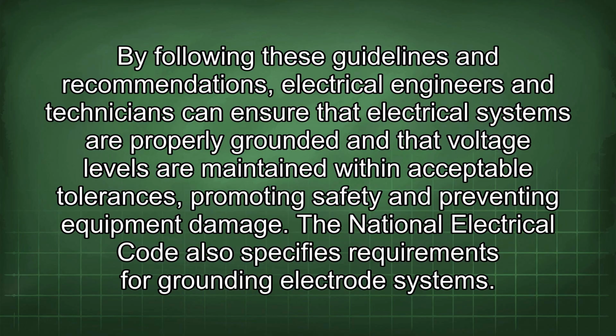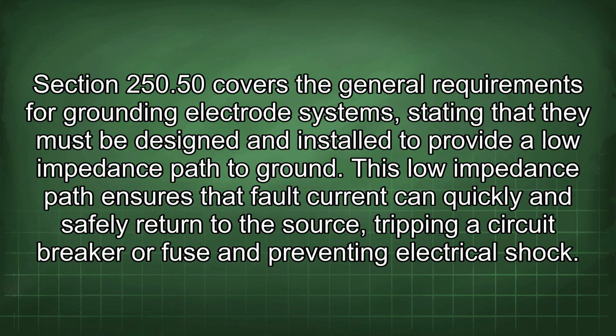The National Electrical Code also specifies requirements for grounding electrode systems. Section 250.50 covers the general requirements for grounding electrode systems, stating that they must be designed and installed to provide a low impedance path to ground. This low impedance path ensures that fault current can quickly and safely return to the source, tripping a circuit breaker or fuse and preventing electrical shock.